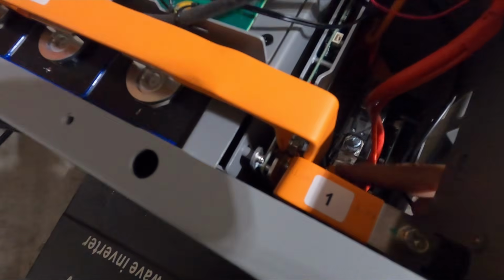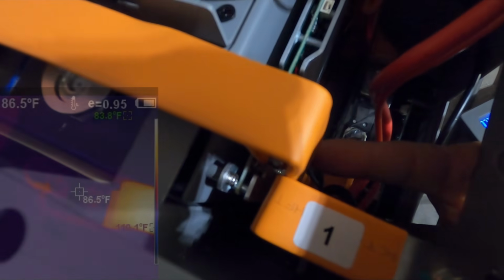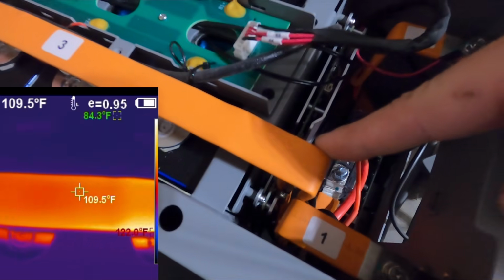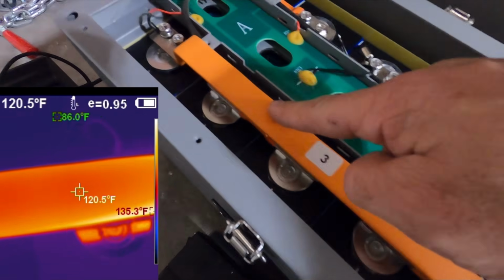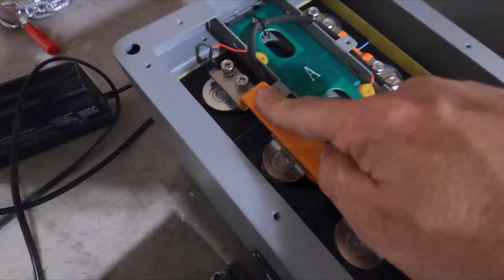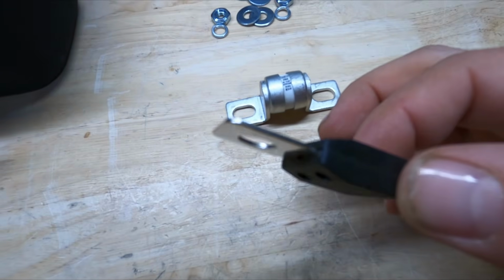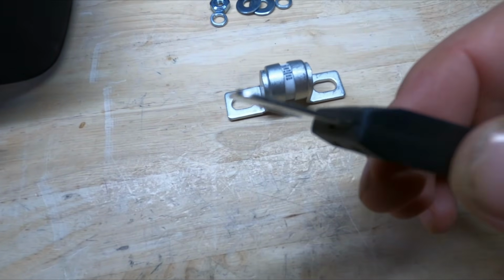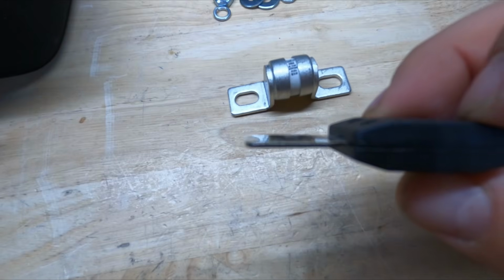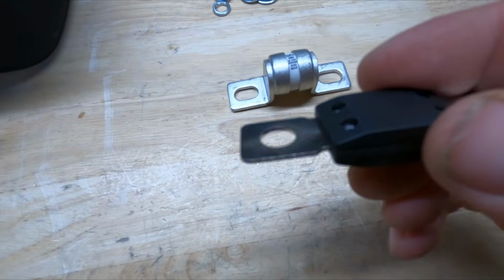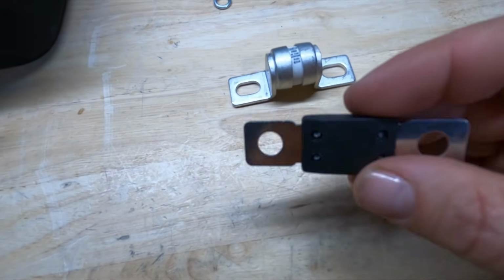You're looking at the bus bar that goes down to the fuse. This part is extremely hot right there, where it contacts the fuse terminal. And it's superheating the bus bar all the way up, and as it travels down the bus bar, it gets cooler and cooler all the way to back here, and this is the coolest point. And that's the problem with these mega fuses. They got a very thin terminal. So all that current is forced to go through that terminal, causing a lot of heat.